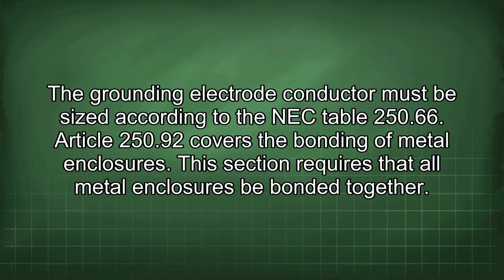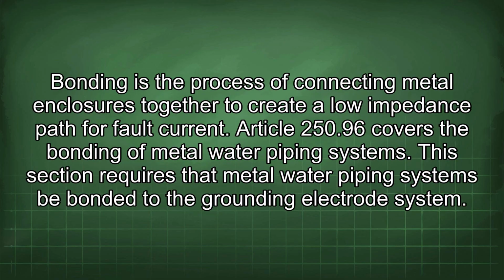Article 250.92 covers the bonding of metal enclosures. This section requires that all metal enclosures be bonded together. Bonding is the process of connecting metal enclosures together to create a low impedance path for fault current.